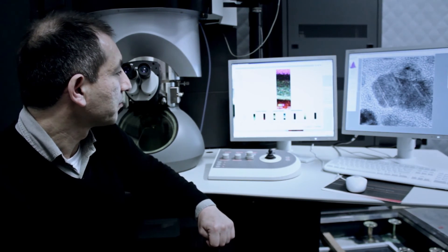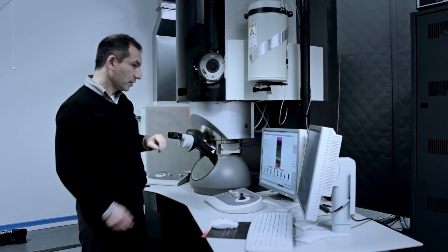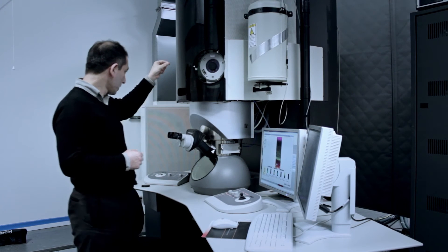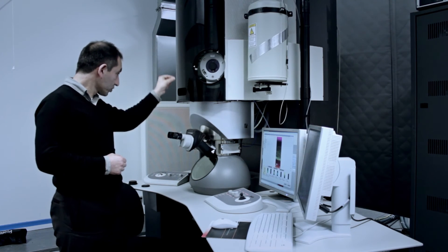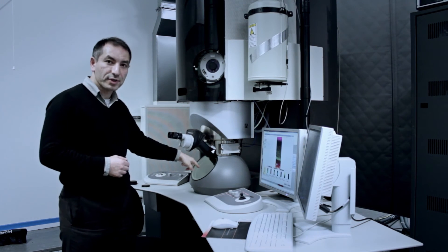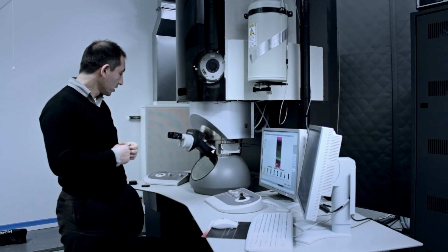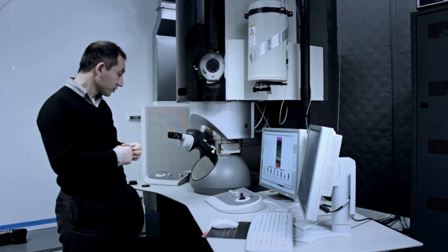So it's our most powerful TEM microscope for stability and resolution. The sample is inserted here, in the sample chamber, through the sample rod. And then the electrons go transmitted through the sample, hit the screen, viewing screen here, which we view through fluorescent phosphor screens.